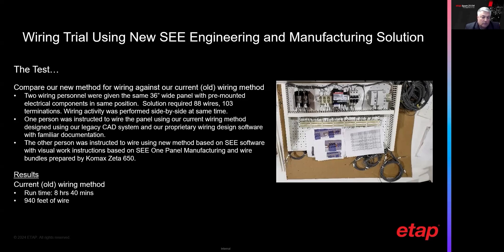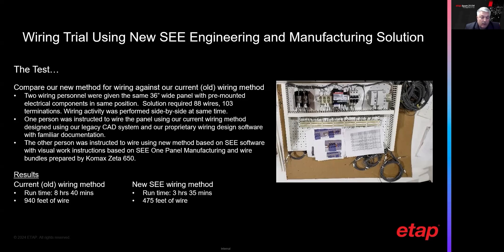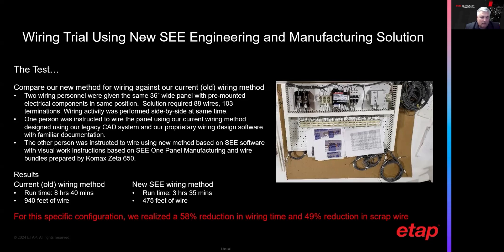Here are the results. The first person doing the wiring the old way: the runtime took about 8 hours and 40 minutes, and they used about 940 feet of wire. The second person using the new method: the runtime was 3 hours 35 minutes and 475 feet of wire. You might ask why we had less wire — well, there was a lot of scrap in the old method because they pull wire longer than they need and end up cutting it to length once it's installed. Whereas with the Komax wires, we calculate that length and cut it on the machine before it's handed to the wiring personnel. In this particular configuration, we realized a 58% reduction in wiring time and a 49% reduction in scrap wire.